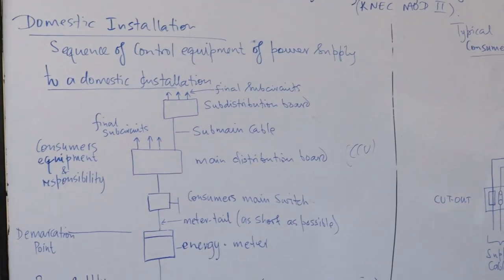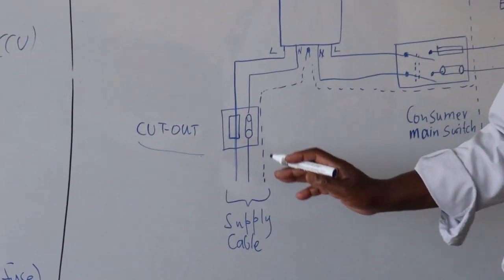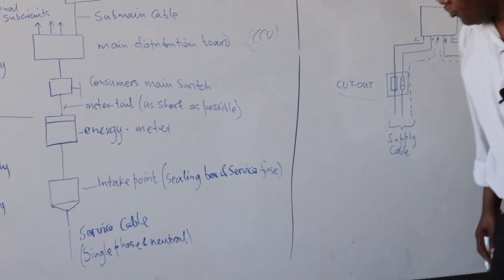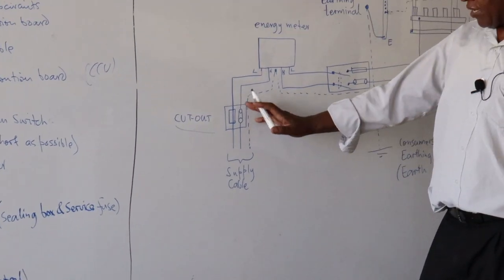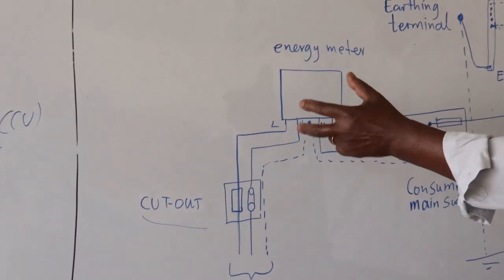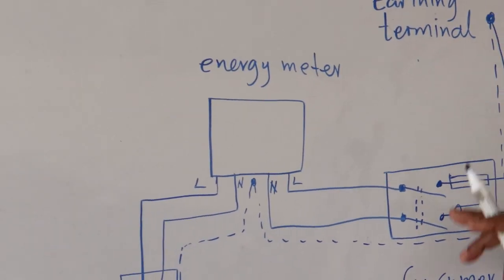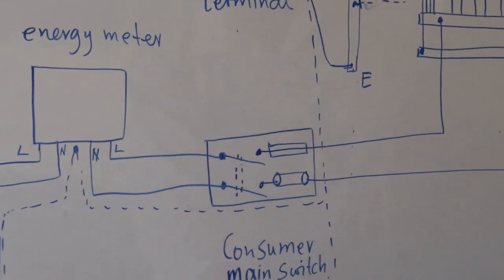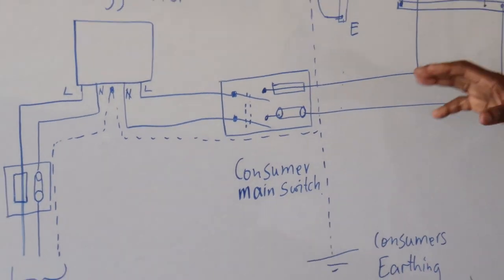Here you have a typical wiring diagram corresponding to the single line diagram I've drawn. The power supply cable comes in. There is what we call the cutout, which I've referred to as the intake point. There's usually a fuse and a link — again, this is KPLC equipment. Then it comes onto the energy meter. From the energy meter, we go to the main consumer switch, whereby you can isolate if somebody's working. And then from the consumer's main switch, it comes onto the distribution board we talked about.